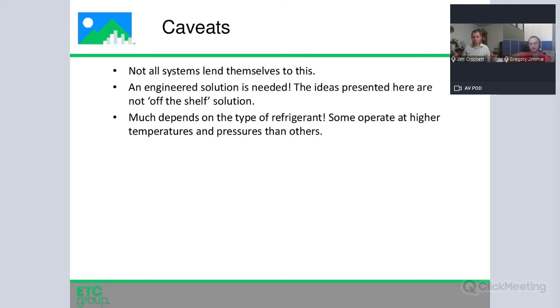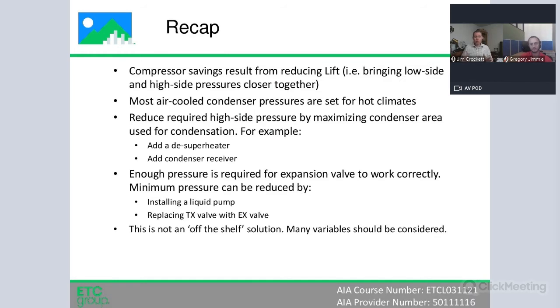So these are good things to think about. Don't go out and buy a receiver and put it on your air-cooled chiller and expect to see savings. This is an engineered solution. It's not just an off-the-shelf thing that you can do. But to recap, compressor savings result from reducing lift, bringing the high side and low side pressure closer together. Most air-cooled condenser pressures are by default set for hot climates. If you're not in a hot climate, look at resetting that default.